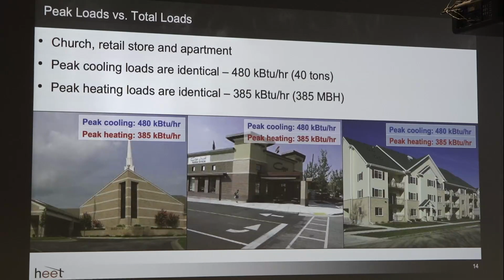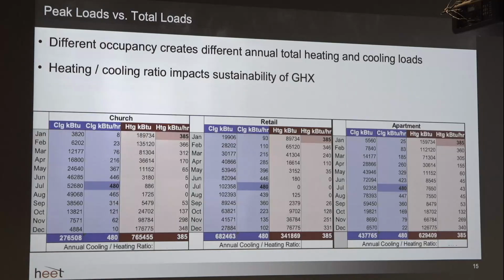So this example illustrates this. So we have a church, a retail store, and an apartment building. They may have the exact same peak heating and cooling loads, 40 tons of cooling and 385 MBH of heating. But due to the difference in occupancy of those 3 different buildings, the total heating and cooling loads are going to change quite dramatically, right?